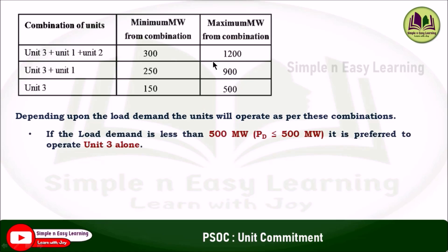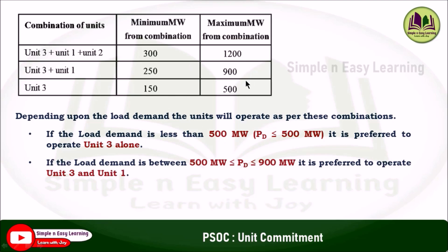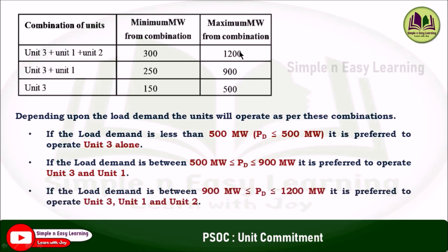If load demand is less than 500 MW, it is preferred to operate unit 3 alone. If load demand is between 500 and 900 MW, operate unit 3 and unit 1. If load demand is between 900 and 1200 MW, operate unit 3, unit 1, and unit 2. This is the unit commitment solution based on the priority list method using full load average production cost.